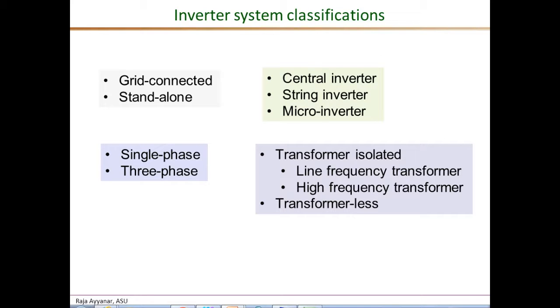Finally, based on the type of PV array configuration, the number of inverters used, and the type of grid connection, we can have three more types: central, string, and micro-inverters. The central inverter is a single large inverter for an entire array of series-connected PV panels. The string inverter is one inverter per series-connected string, used mostly in residential applications. The micro-inverter has one inverter per panel connected directly to the AC grid.